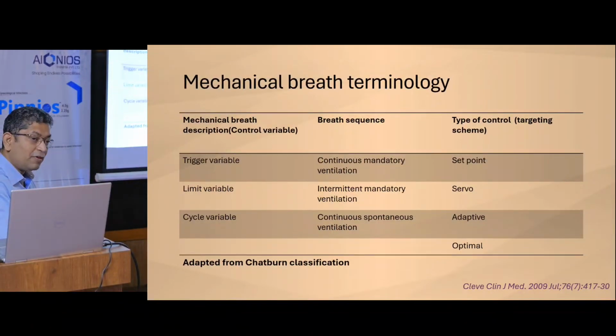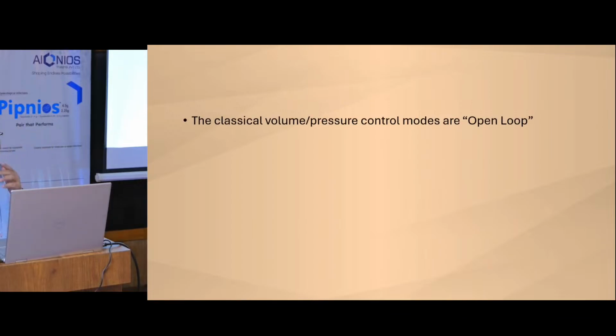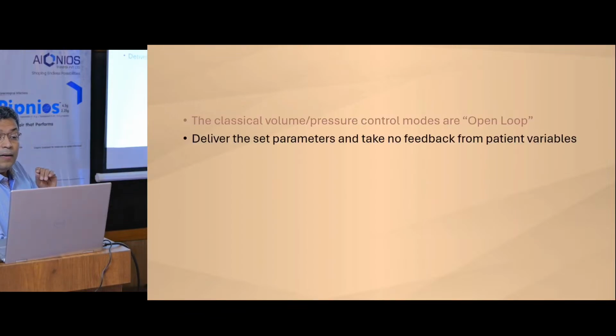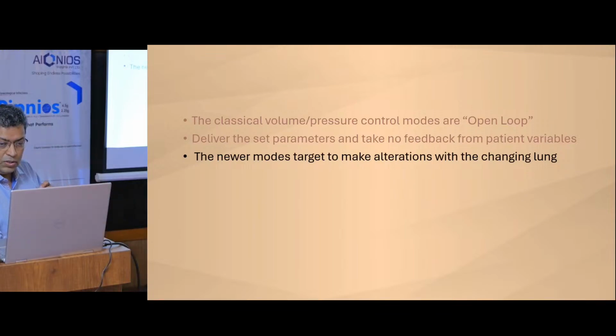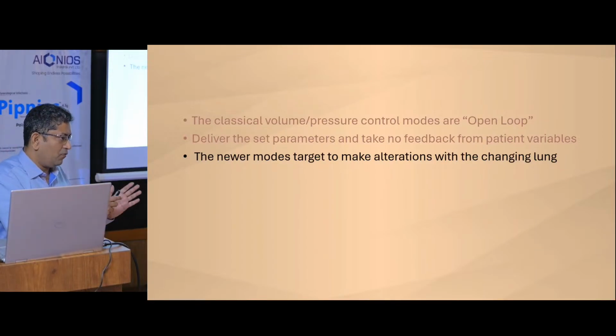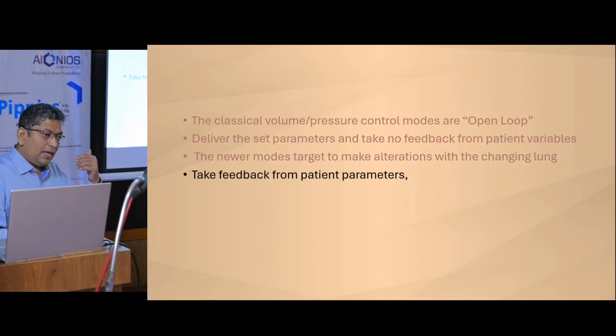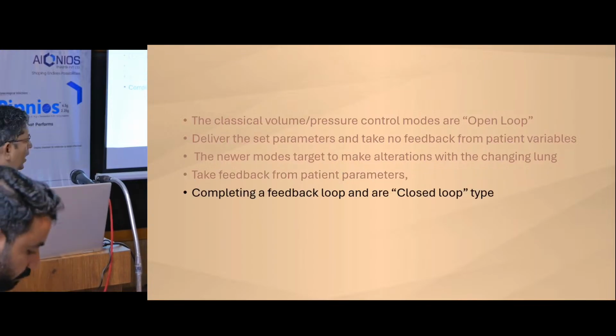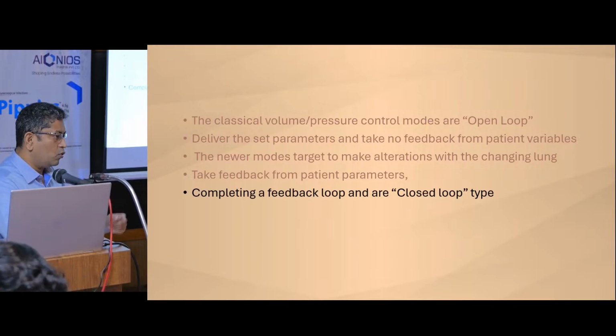This is adapted from Chatburn classification. If you are interested in looking at it, look at it after your exams. So the classical volume and pressure controls are called open loops. That means there is no feedback from the patient. You set a target and the ventilator delivers that. Now, newer modes target to make alterations. When there is alteration in the lung, the target for the newer mode can change. So that is the difference from the older modes to the newer. They take feedback from patients and make it a closed loop feedback.